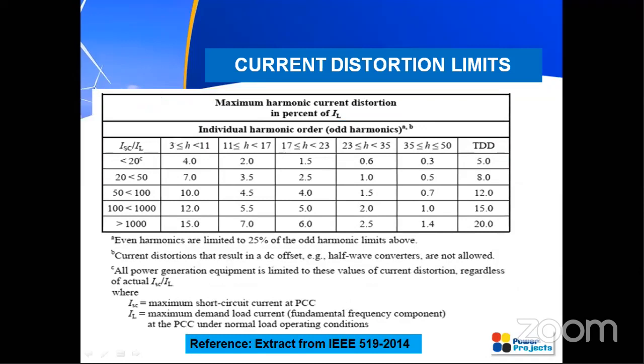Coming to the current distortion limits, we will be checking this with the short circuit ratio. I have told you that the ratio of short circuit current to load current determines the strength of the system. Based on that value, we have to check the individual harmonic, whether it is lying within the particular limit or not. For this, we have to know the short circuit contribution and load current of the system. From that, you check the range, and in that particular range, you check whether the corresponding individual harmonic is lying within the prescribed limit or not.